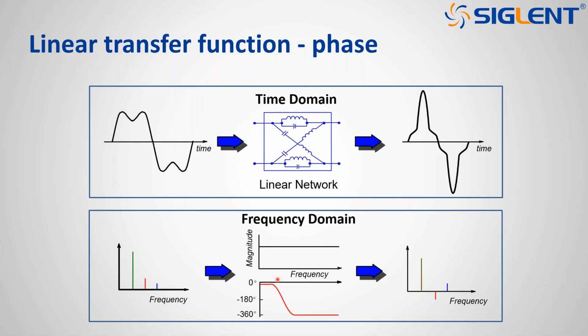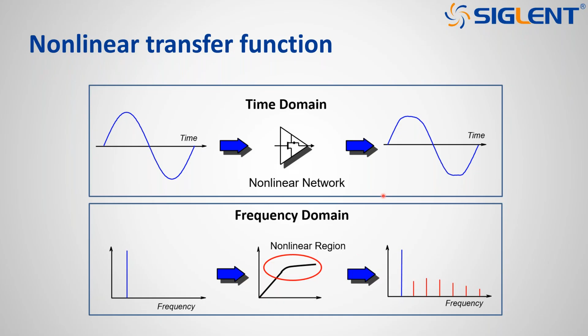Looking at nonlinear transfer functions, take an amplifier as an example. The amplifier has a linear part, and when it reaches saturation it moves into a nonlinear region. If your input frequency and power fall exactly in the nonlinear region, the inputted sine wave gets disturbed, as seen in the time domain view. In the spectrum, this generates harmonics and subharmonics, which you typically don't want because it's energy loss — you then have to filter it out again, requiring additional effort. This is an important measurement when testing with VNAs.